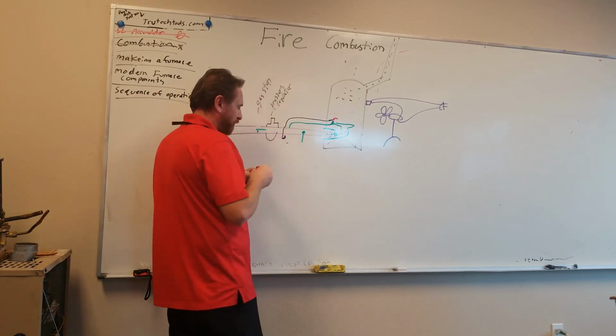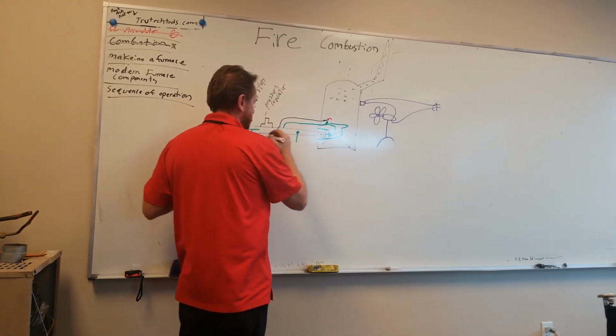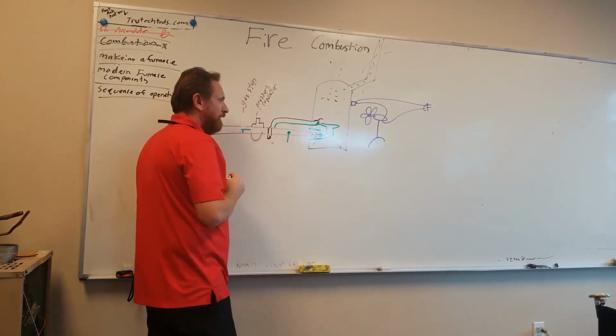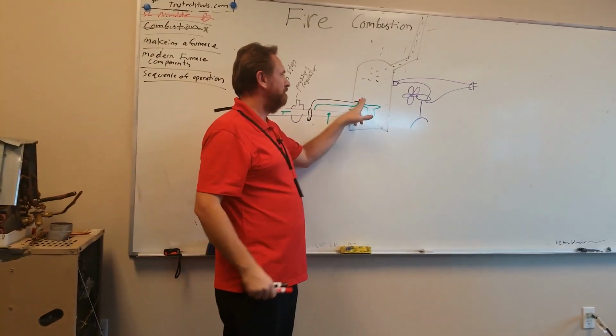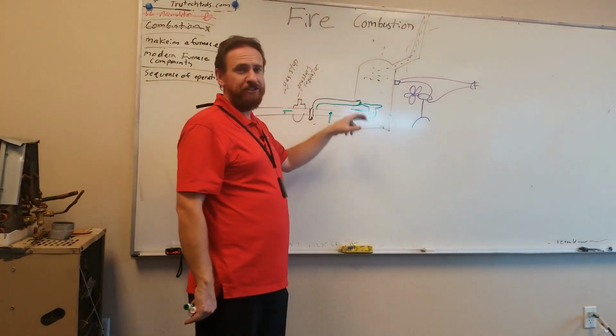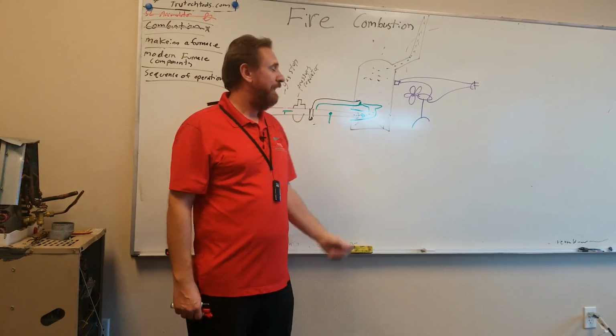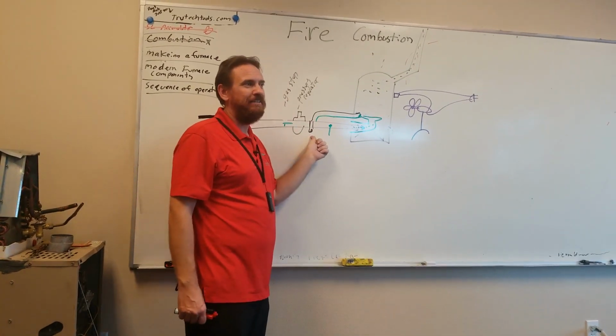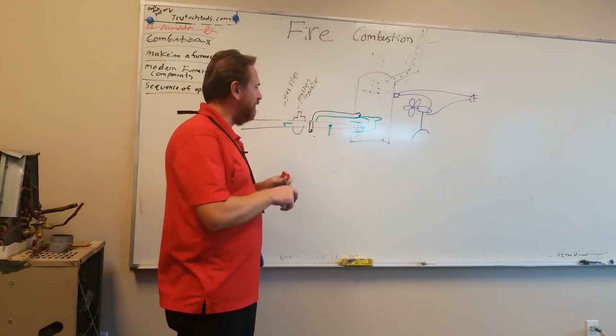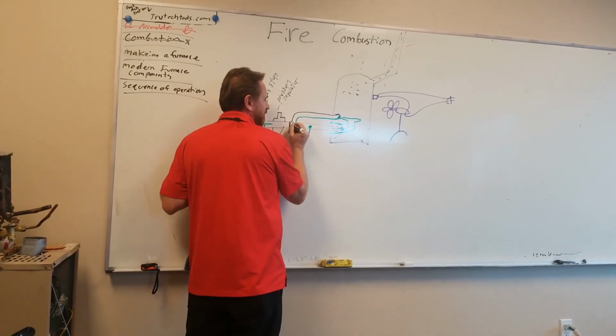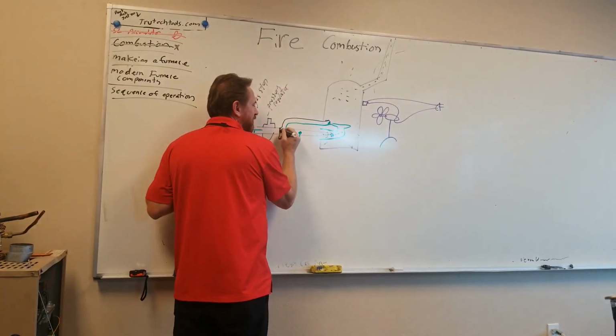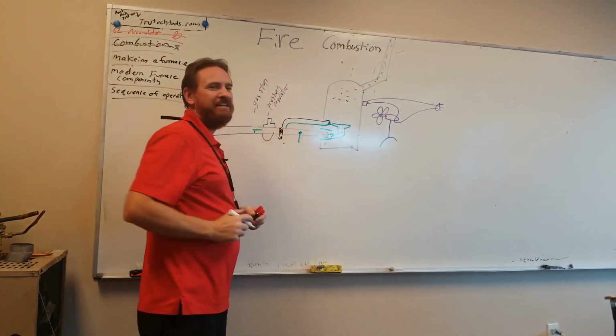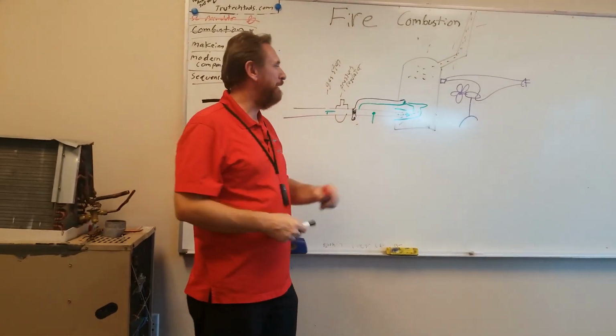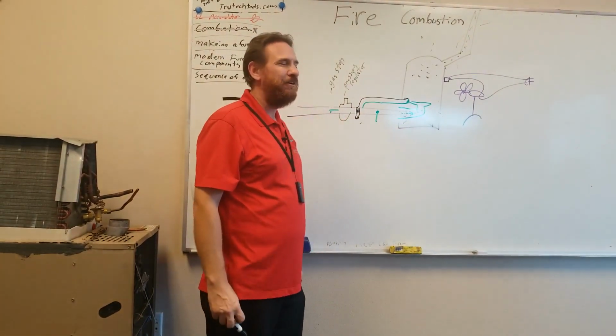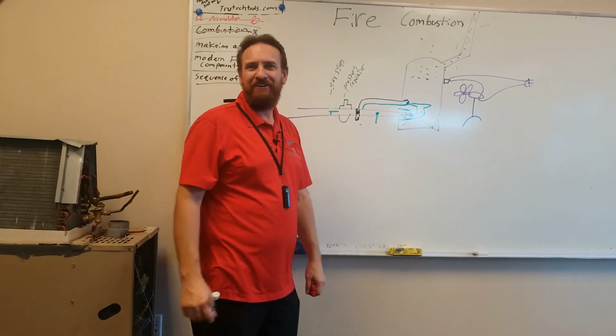So we have a little solenoid valve right here. If the pilot light goes out, are we going to create voltage and current? Is there going to be anything to energize the electromagnet? So if the electromagnet goes out, what's going to happen to this next little valve right here? It's going to close. Now if this valve closes and I open this valve, is any gas going to flow? No. Is the pilot light going to let gas flow? No. But now I need to relight it, correct?